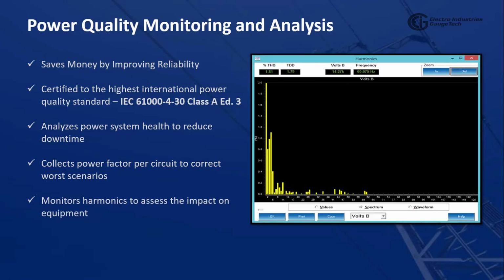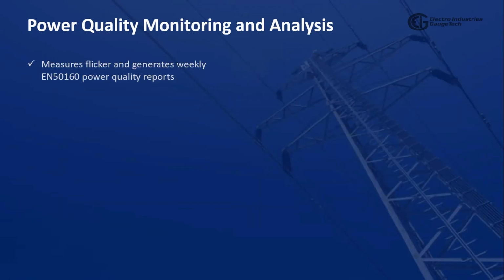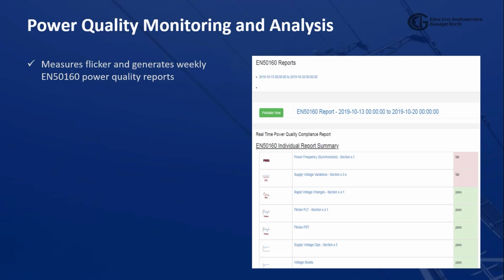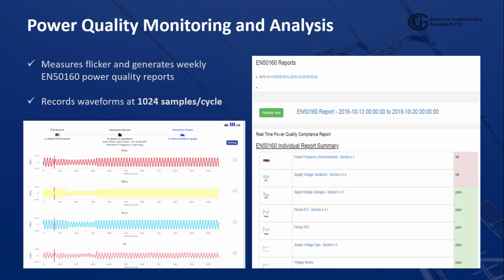The image here shows the harmonic spectrum analysis, measures flicker and generates weekly EN50160 power quality reports. In the image shown here, you can clearly notice the page with the EN50160 power quality reports. Records waveforms at 1024 samples per cycle.